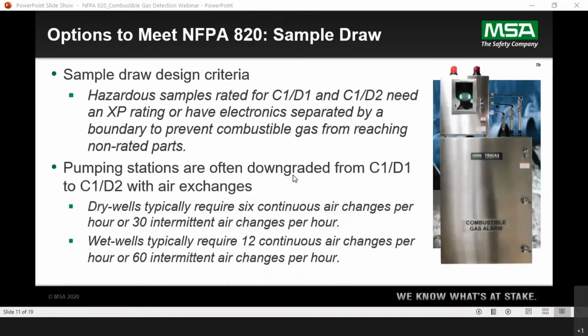So, sample draw design criteria. The important thing about drawing samples is where is the sample located and what is the hazardous rating for the location of, if you will, the filter where it's installed. And if they're rated Class 1, Division 1 or Class 1, Division 2 per the NEC code, then you need to have an XP rating for your electrical components, or have the electronics separated by a boundary so that you prevent combustible gas from reaching the non-rated parts.